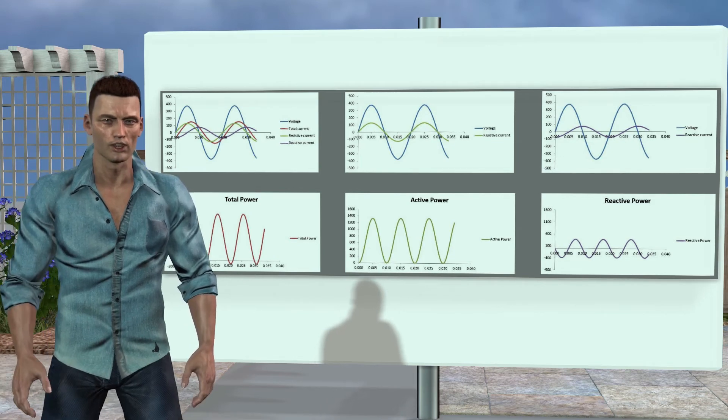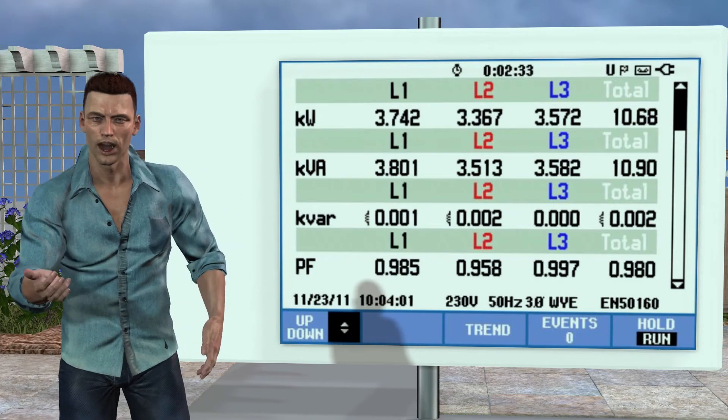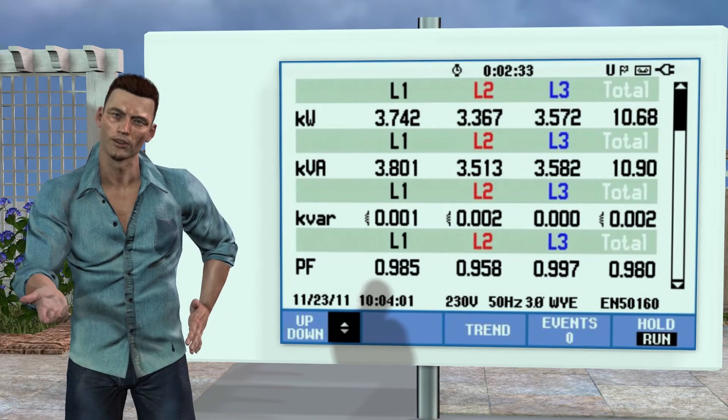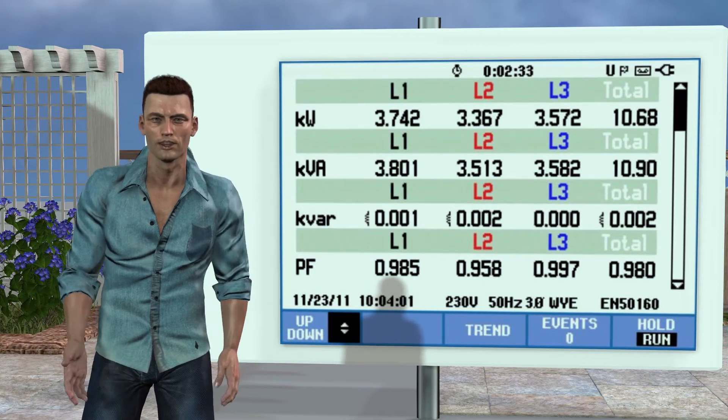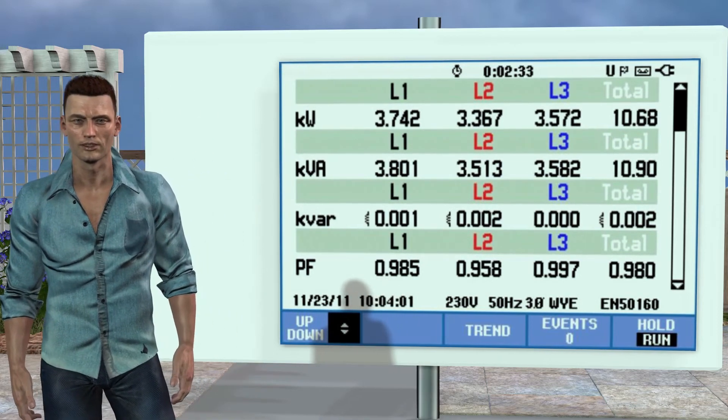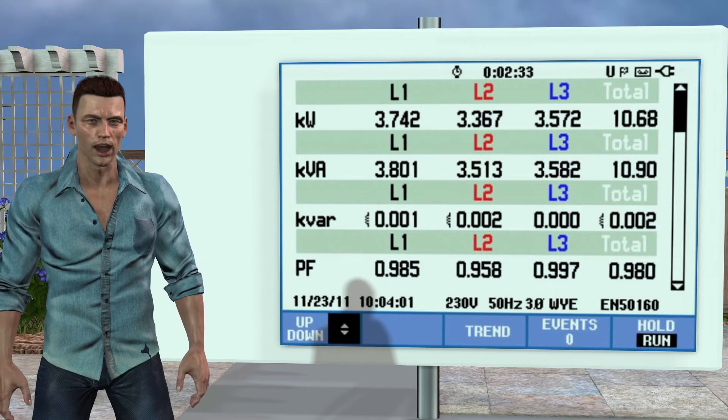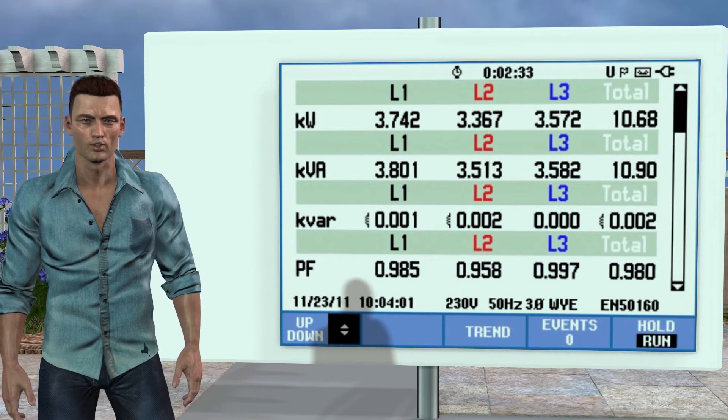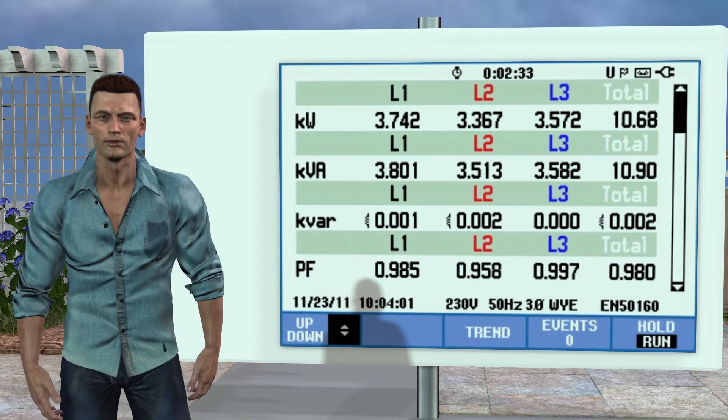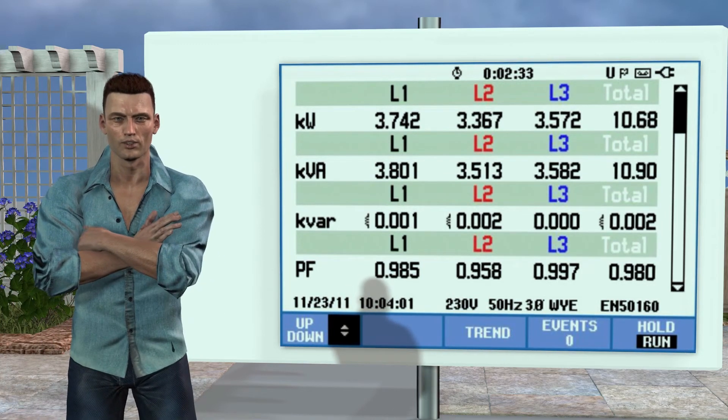However, when we use a power quality analyzer to analyze these powers, to simplify their study and to be able to quantify them, RMS values are used, but in this case, we cannot add them arithmetically, as they are really vectors, and as a consequence, for adding them, we must use a vector sum, considering the phase angle, phi, between voltage and current.